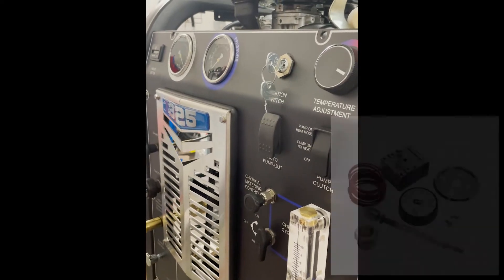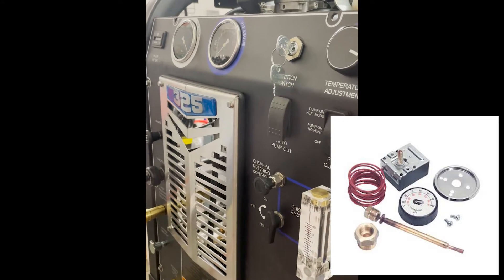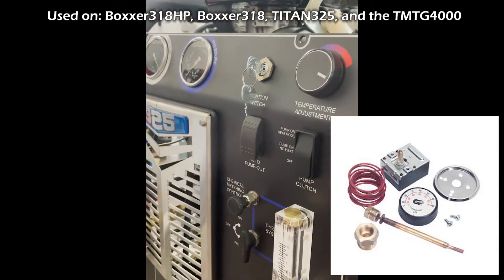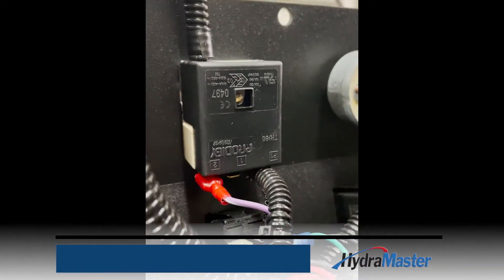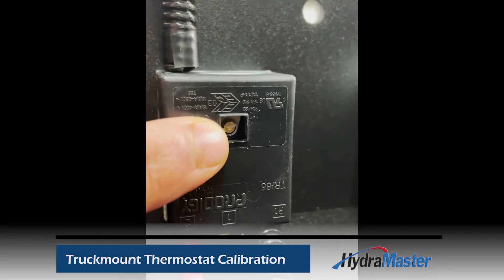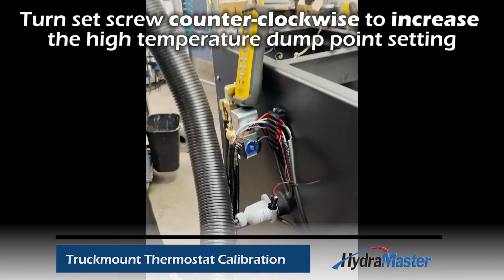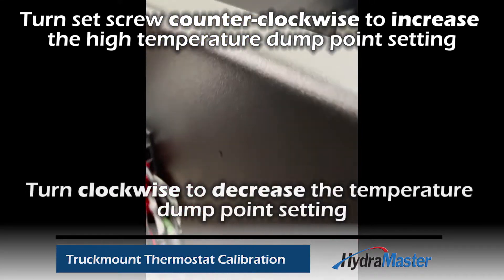Hey everybody, here at HydraMaster in the test room with a Titan 325. We're going to show you how to calibrate the temperature adjustment thermostat, which uses a potentiometer for adjustment. This is going to adjust the high temperature setting that the dump solenoid on the waste tank uses to dump water at a set temperature into the dump tank.